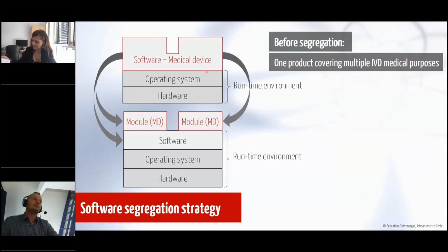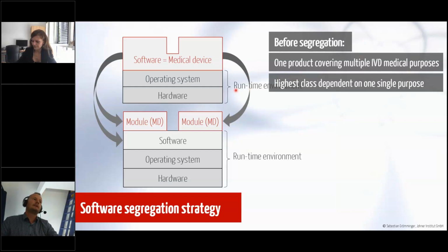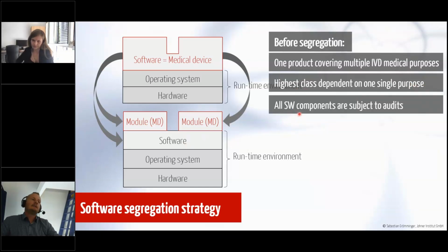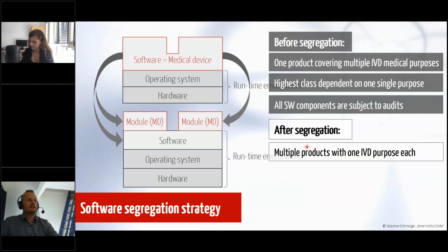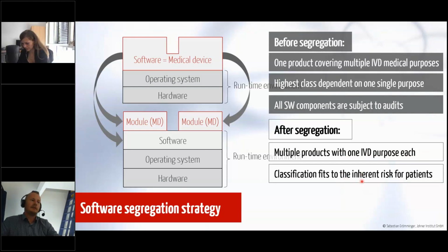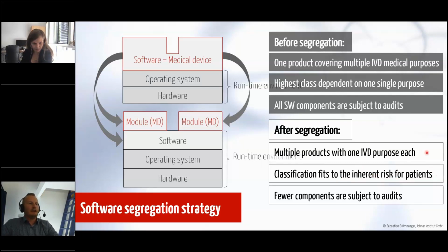Before segregation, you have one product covering multiple IVD medical purposes, and the highest class is dependent on one single purpose. It falls under the highest class dependent on the most critical purpose, and then all software components are subject to audits by the notified body. After segregation, you have multiple products with one IVD purpose each, and then the classification would fit the inherent risks for patients dependent on the clinical claims of that module. There you would have fewer components which are subject to respective audits and approval by notified bodies on the side of the technical documentation.